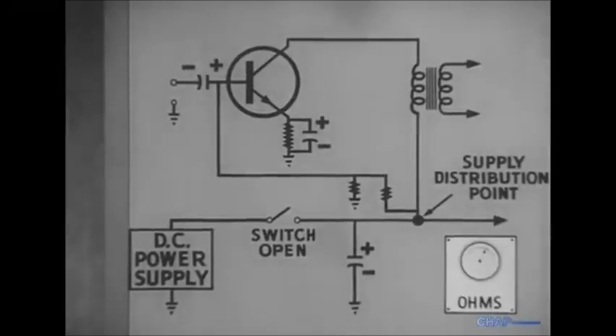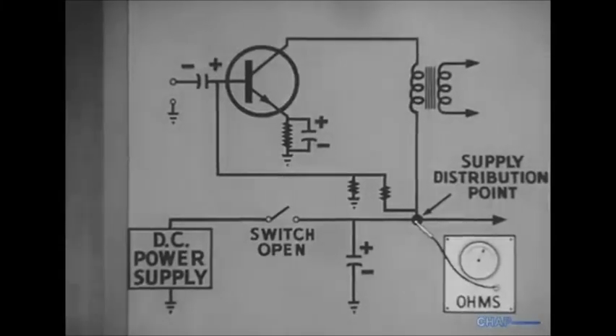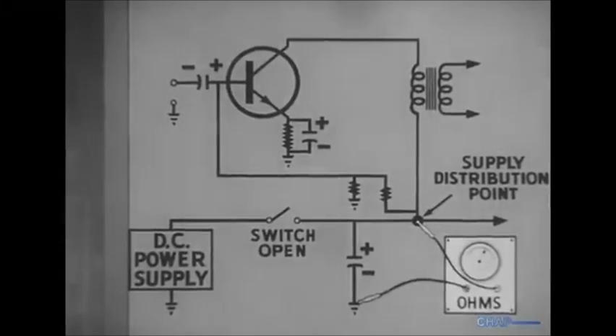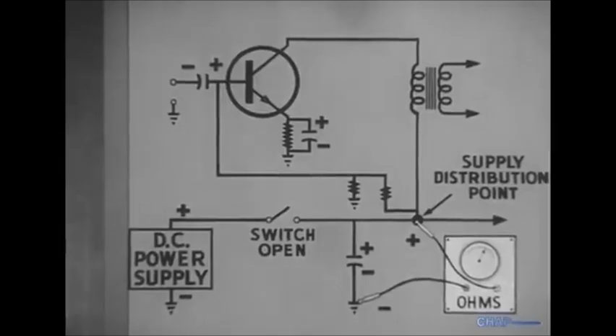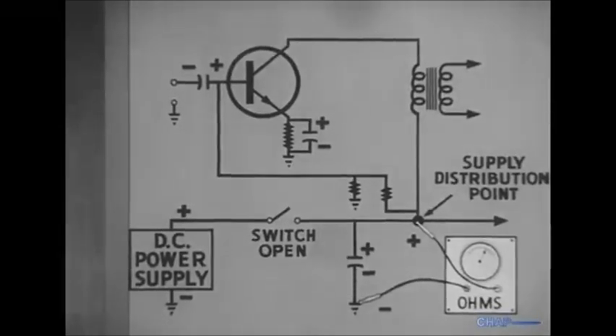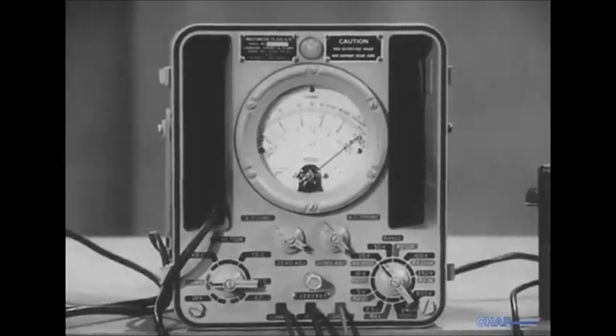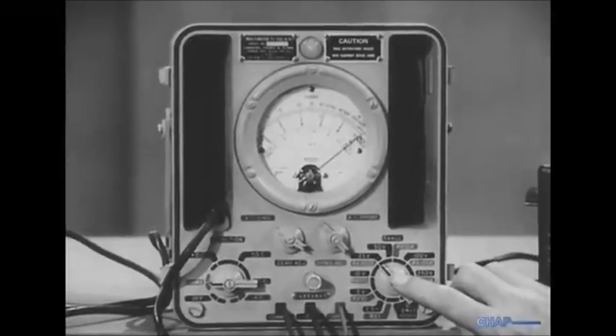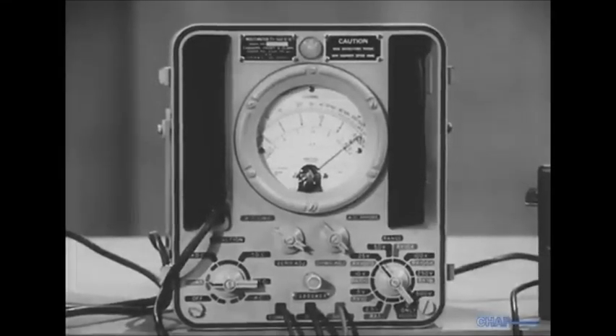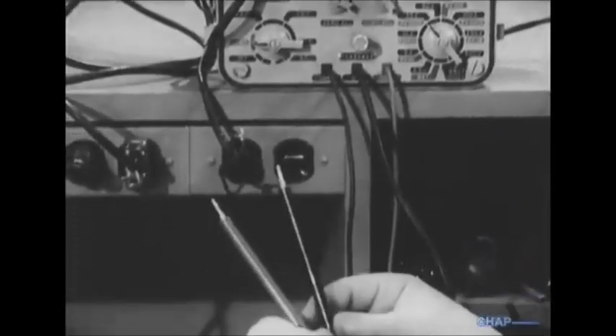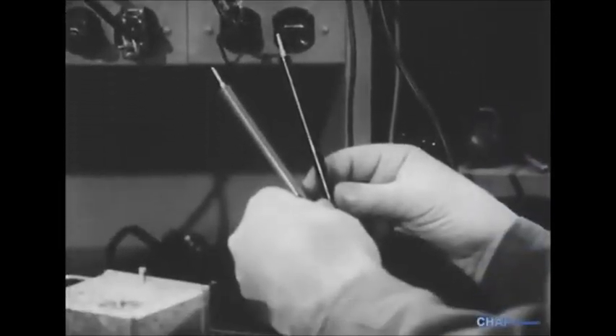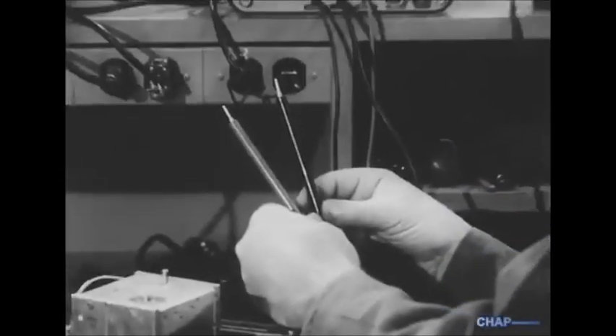When we check for a possible short by measuring the resistance between the supply distribution point and ground, the ohmmeter puts out a test voltage. We have to be absolutely sure about the polarity of this output, and also take care that the output voltage doesn't exceed the value normally present in the circuit. The ohmmeter's output voltage and current are determined by the range switch setting. Observing polarity is simple enough in theory, but in practice, the unmarked probes may lead to a mix-up.